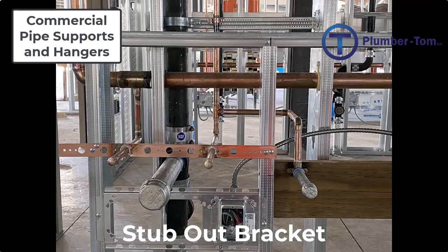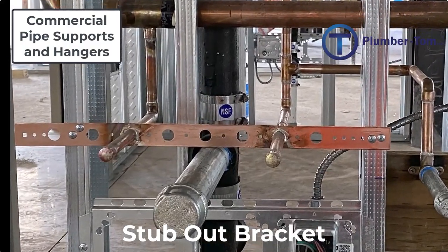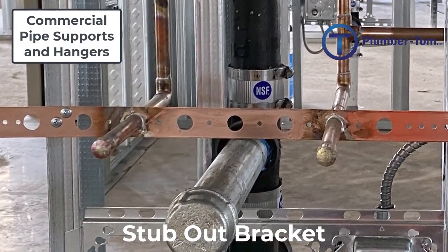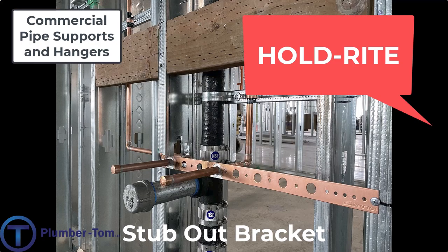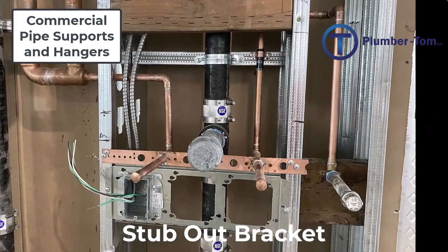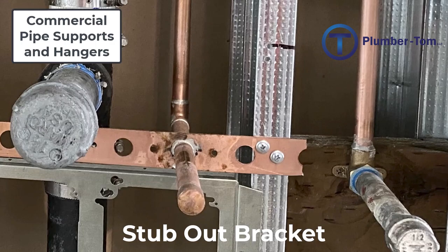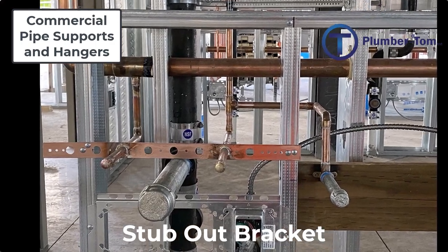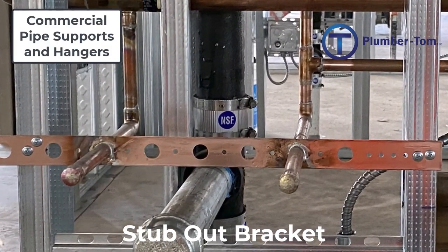Let's have a look at copper stub-out brackets. Copper stub-out brackets are designed to hold copper pipes as they extend from inside the wall into the room. The copper pipe fits through holes specifically designed to hold that pipe size and is then soldered to the bracket. These are sometimes called Hold-Rite brackets after a common manufacturer. They are attached to the frame wall structure using self-tapping metal screws, must be set level so pipes come out at the same elevation, and are generally used just for stub-outs near or behind plumbing fixtures.